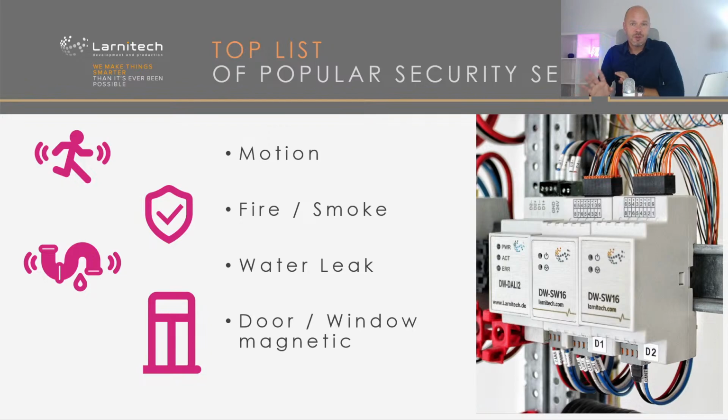It is important to understand that our system is not a fire control system, for example, and also is not a certified security system. These are all functions of our system, but we are not certified to be installed on commercial projects, for example. So if you want a real certified system, it is possible also to install a fully certified system and connect its status contacts to our system as well. So you will have a fully independent fire and security system, and then you will have the status inside our system.